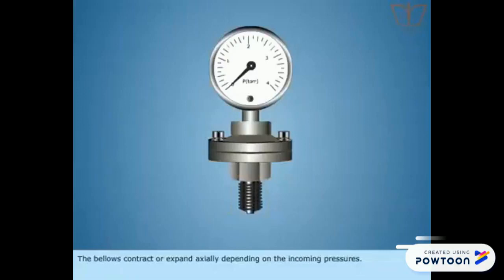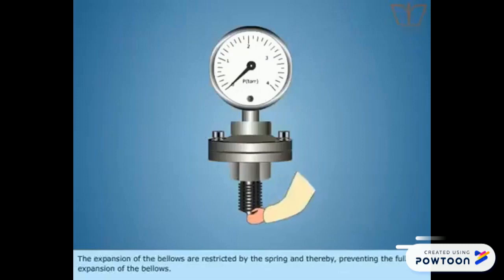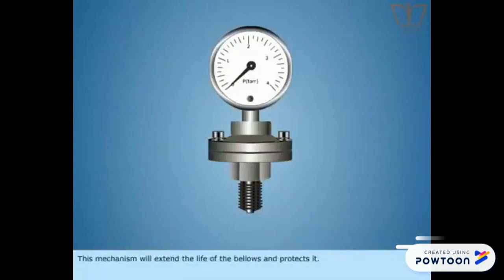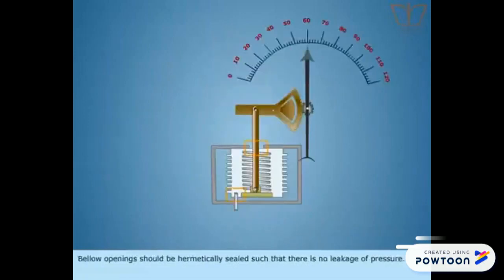Bellows contract or expand axially depending on the incoming pressures. The expansion of the bellows are restricted by the spring, thereby preventing the full expansion of the bellows. This mechanism will extend the life of the bellows and protects it. Bellows openings should be hermetically sealed such that there is no leakage of pressure.